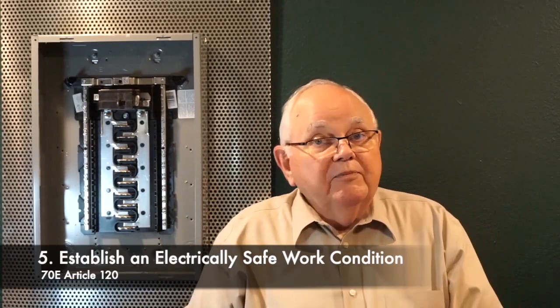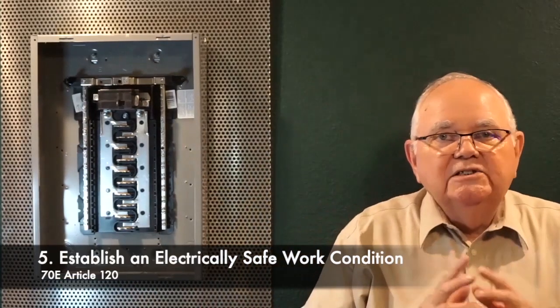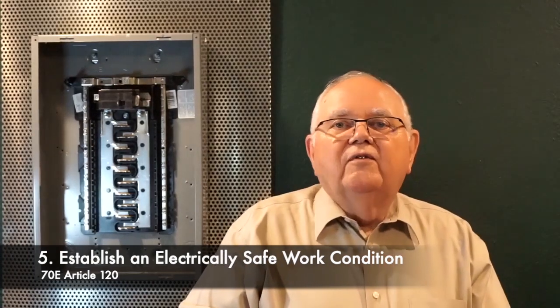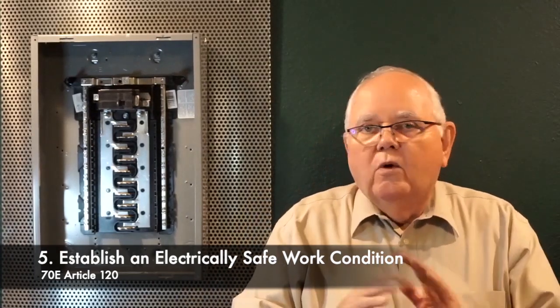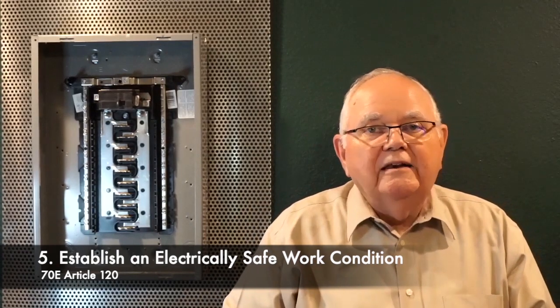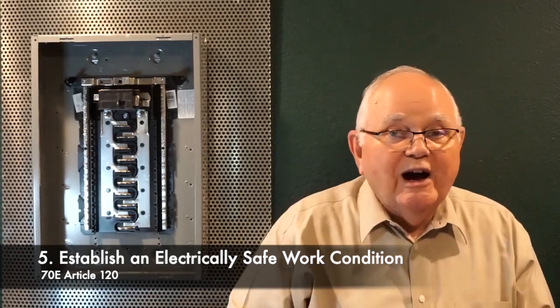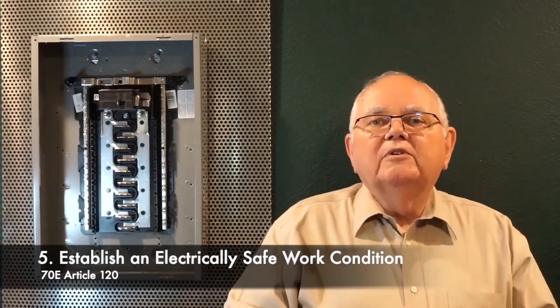Now I'm ready to go inside of that barricade and boundary with all of my appropriate PPE, following all of my company's safe work practices and procedures, and go to work on this equipment and verify an electrically safe work condition. NFPA Article 120 gives you 8 steps in order to verify an electrically safe work condition. Once again, big topic. You want to go through all of that in another training session. In fact, you're required to do that. Your lockout tagout program is required to be audited annually then. And one of the most important parts of the lockout tagout program is the live dead live test.